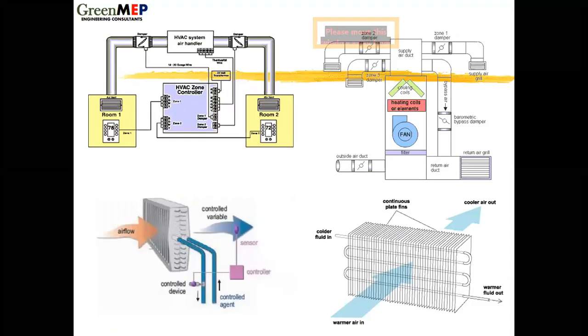When the valve is open, that means more chilled water per minute. That's a sort of a signal. And the pump speed goes up, because when you open the valve, the friction, the head decreases, and then the flow increases. If you're familiar with how these pumps work. So there is a temperature control problem here.